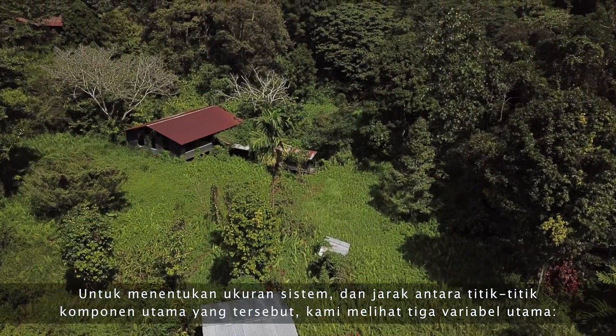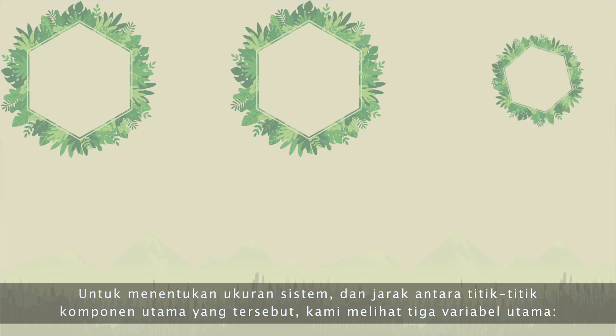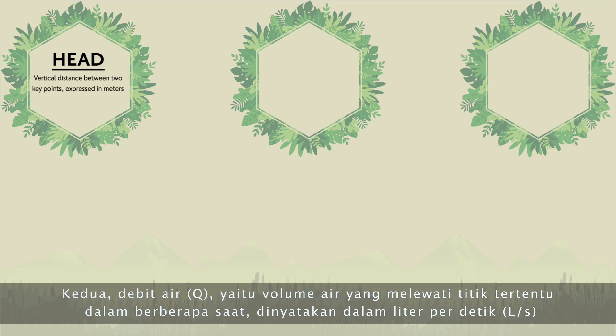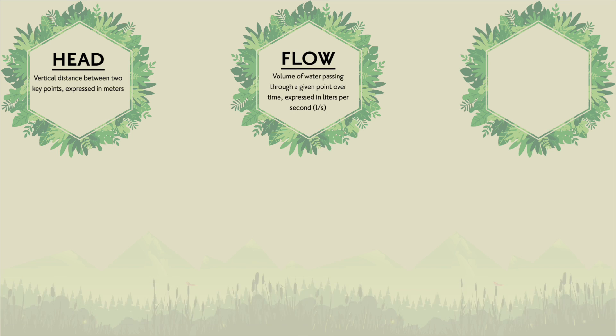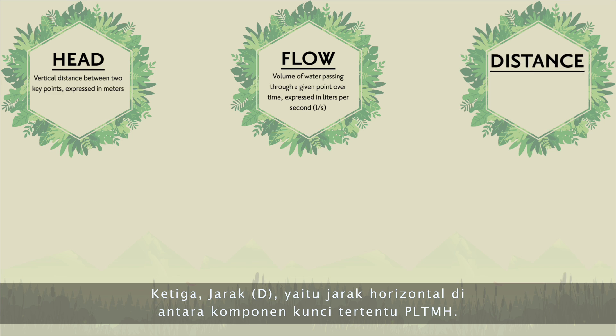To determine the system size and distance between key points during a feasibility study, we are looking at three key variables. First, we're looking at head, which is the vertical distance between two key points expressed in meters. Second, we're looking at flow, which is the volume of water passing through a given point over time, expressed in liters per second. Third, distance, which is the horizontal distance between certain key components of the microhydro system.